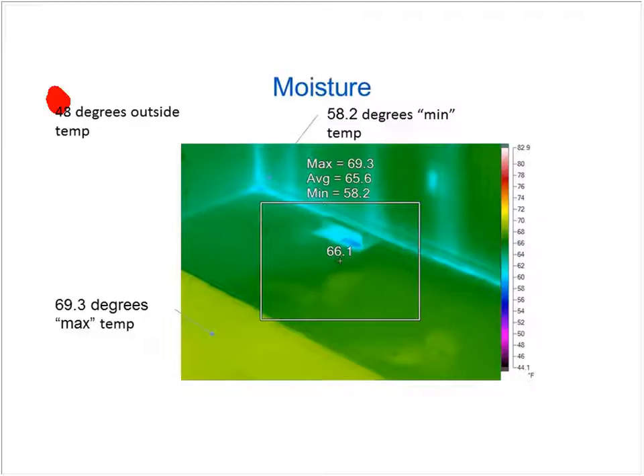The setback furnace is, as far as I'm concerned, probably the kiss of death to a lot of multifamily and lower income properties, because what happens is, and we just had this case in Yakima, Washington. In Yakima's high desert area, low humidity outside. However, in the multifamily property, there was a large population in a small footprint. It was an 800 square foot unit. There were 40 of them, I think it was.